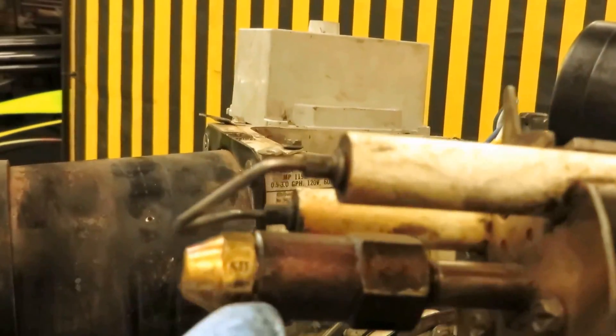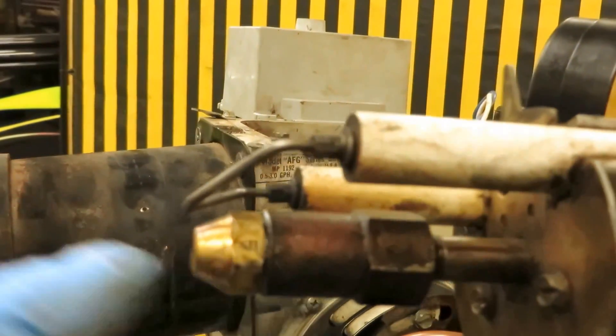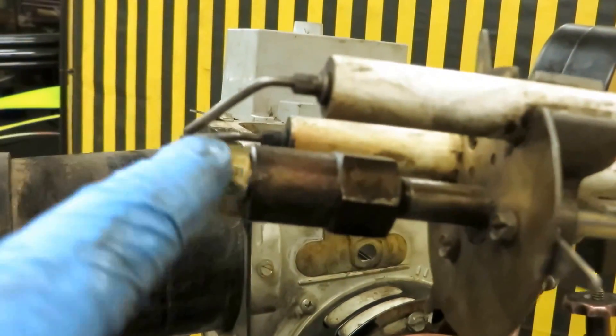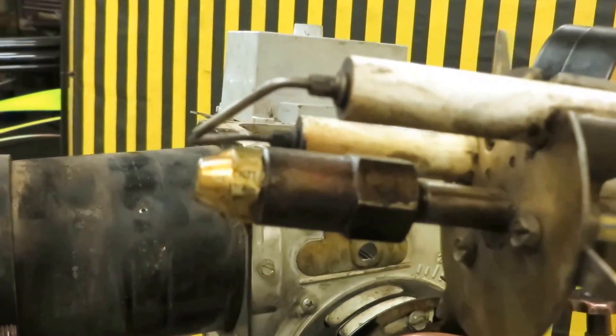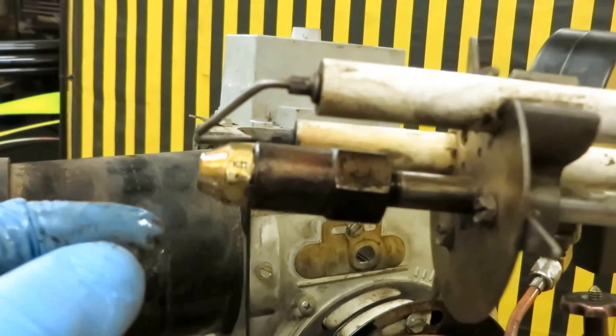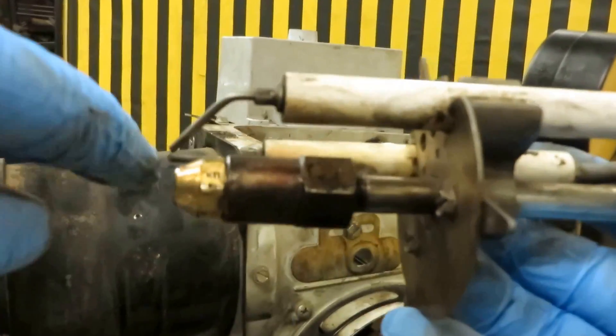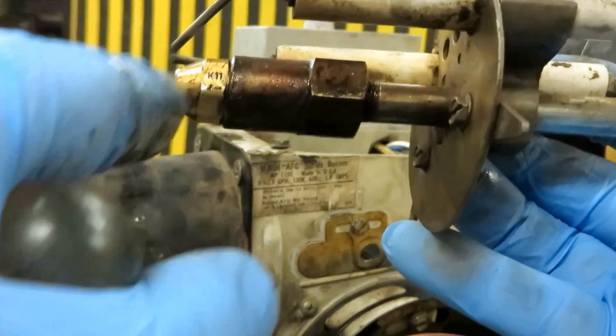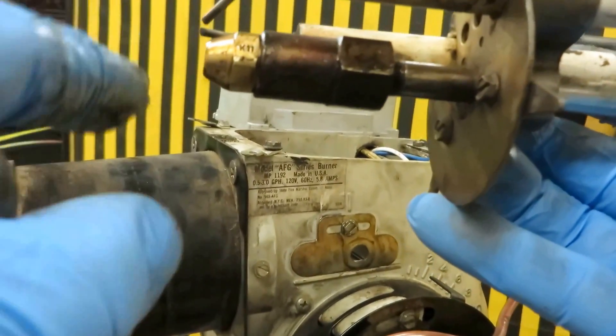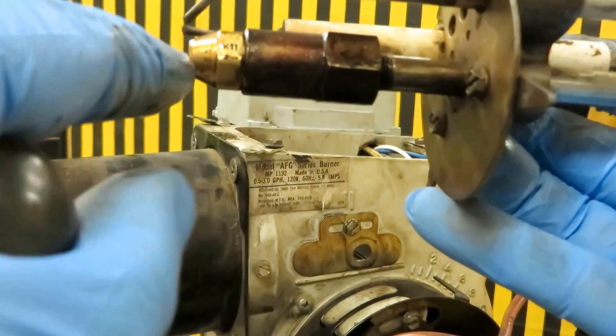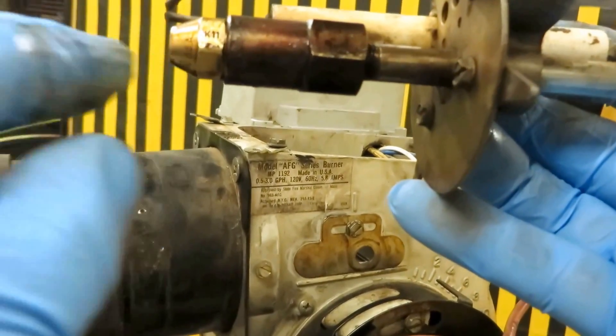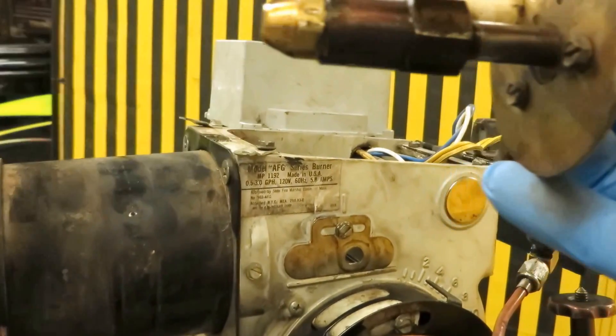Now on the nozzles here, there's different angles and different gallons per hour. An 80 degree nozzle, you're going to have more of an angle like this. A 45 or 60 degree nozzle will have less of an angle, but that's made for a long chamber.